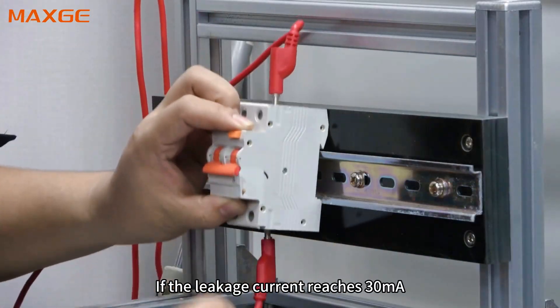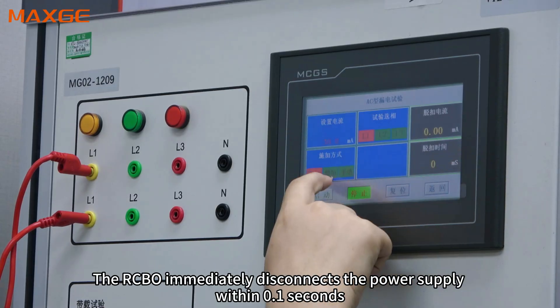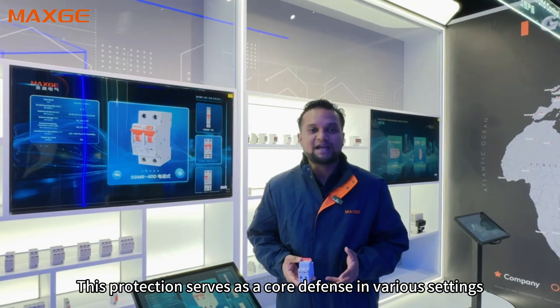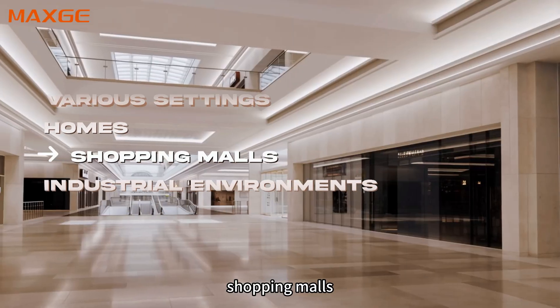Leakage testing: a 500-ohm resistor simulates human body resistance. If the leakage current reaches 30 milliamperes, the RCBO immediately disconnects the power supply within 0.1 seconds, effectively eliminating hazardous voltage. This protection serves as the core defense in various settings including homes, shopping malls, and industrial environments.